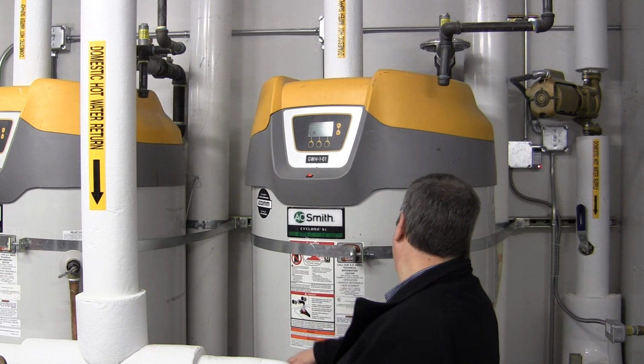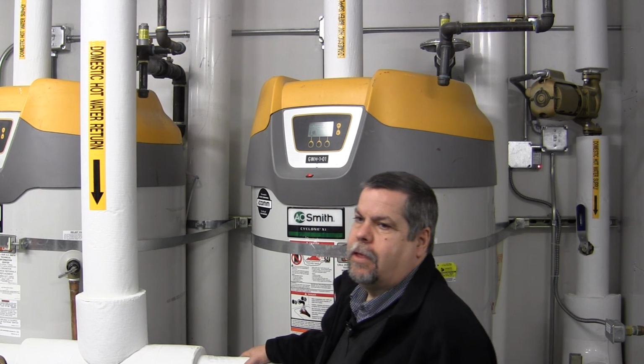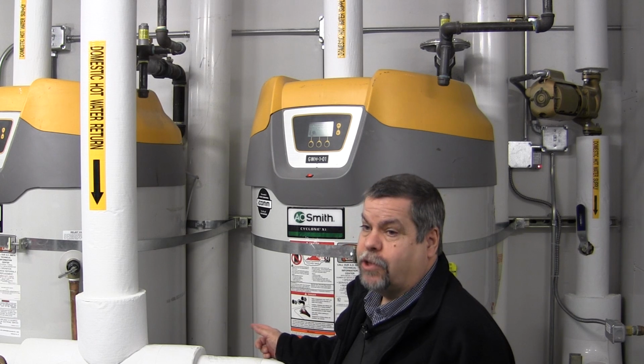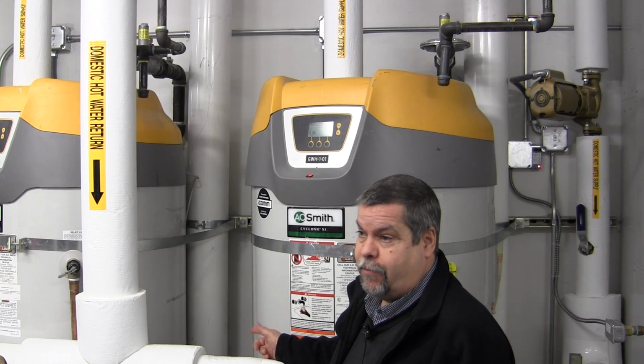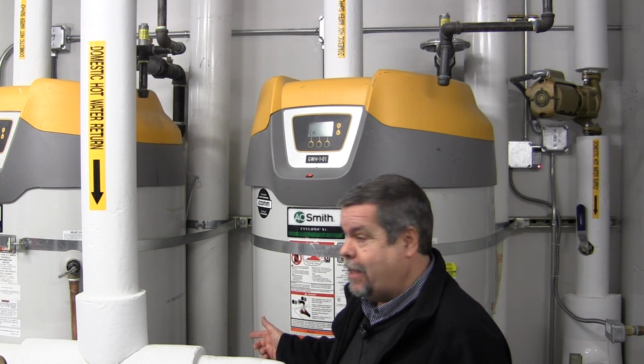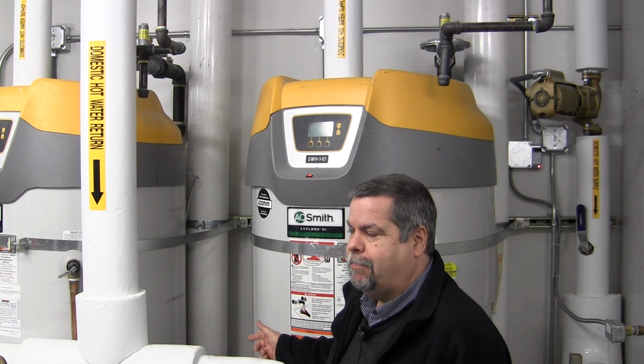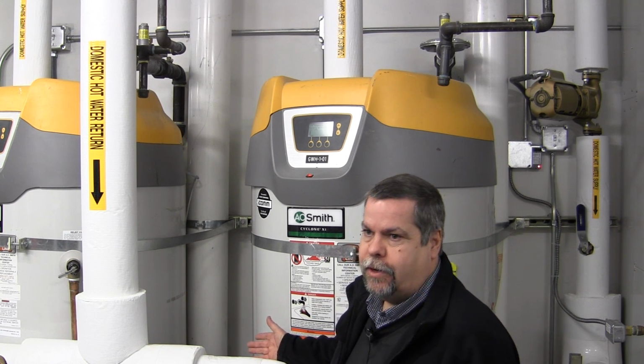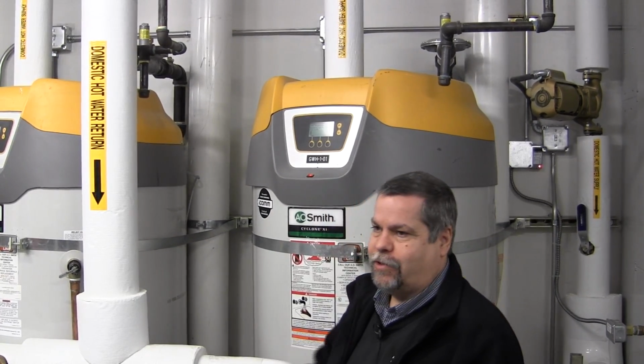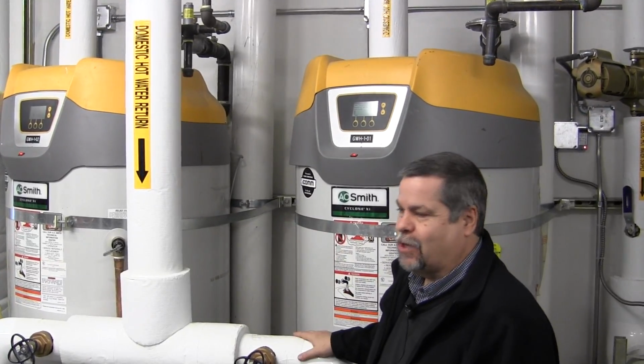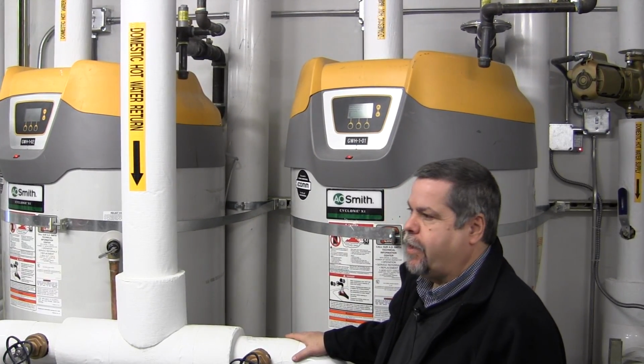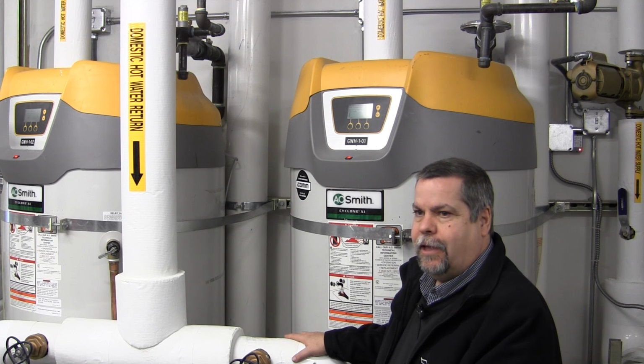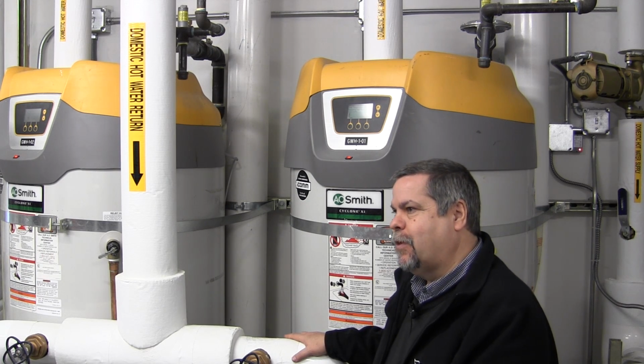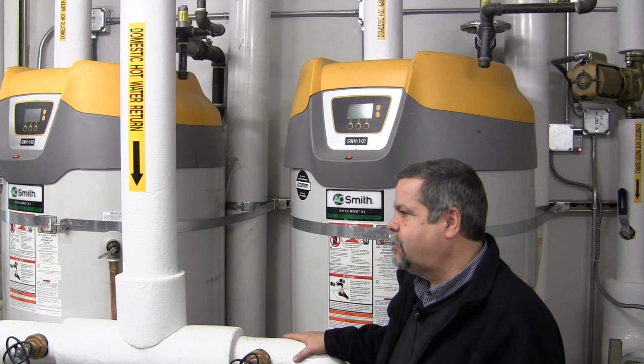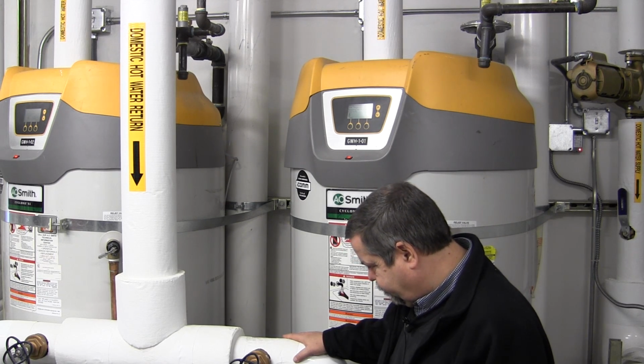Same for your boilers, your tanks, everything that's over 199. You'll have quite a few in this room. These are also ASME model heaters. In the state of Oregon, if you're over 199,000 BTUs, you have to be ASME tank construction. That's a construction code that ensures that the welders that welded the welds were certified, and there's a whole inspection report. It's a quality control standard. They do make this model in a non-ASME, and if this went bad and you were to put a non-ASME in there because it was less money, it would get flagged because this is an ASME state. Yeah. So you'll have your annual inspections.